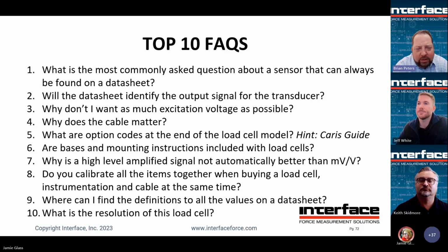All right. And what is the resolution of this load cell? We get asked that a few times. Really, it's a millivolt per volt analog device. So theoretically, it has infinite resolution in terms of output response from force applied. The reality is resolution is typically going to be limited on the instrumentation side. You're going to be looking at your A to D conversion limit in terms of how your instrument can take an analog signal and break it up into digital chunks.